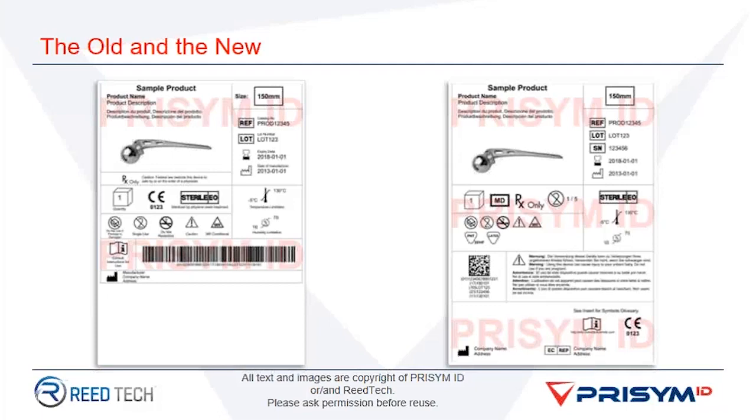Here we've only included, as I said before, 5 languages. Typically this would be a much higher number of languages that you're going to be putting on your main labels, and that will increase the amount of space that the warning section will require. We've changed how we've grouped some of the symbols as well between these two labels. This is worth considering as it may make better use of some of that label space.